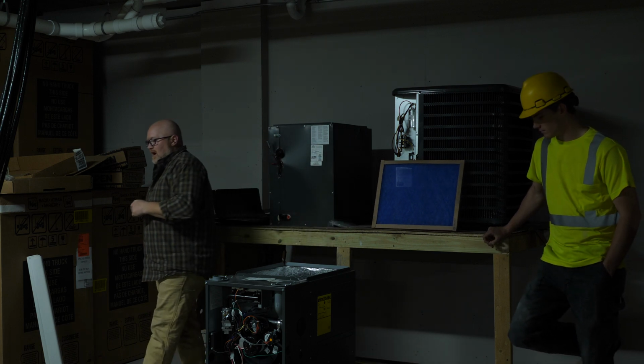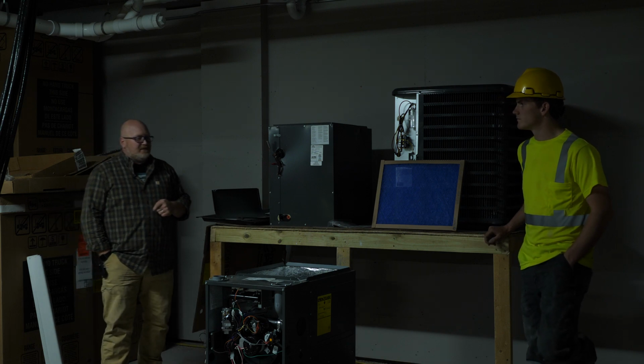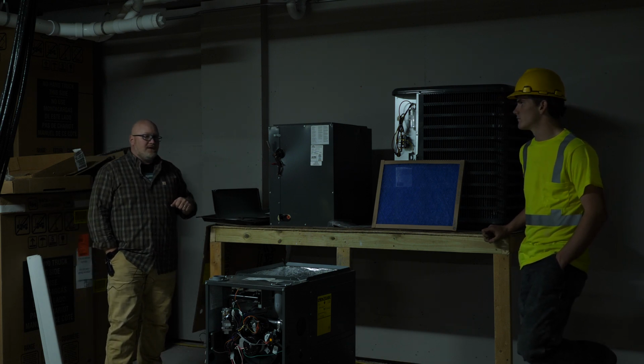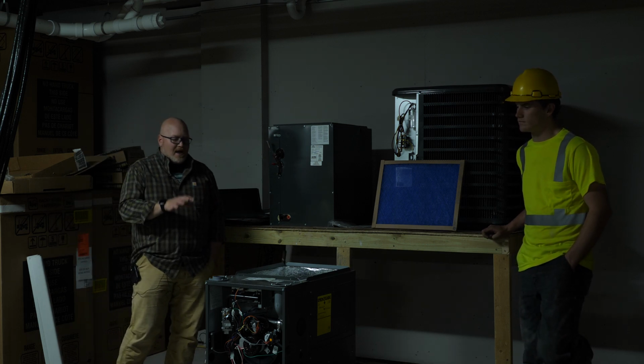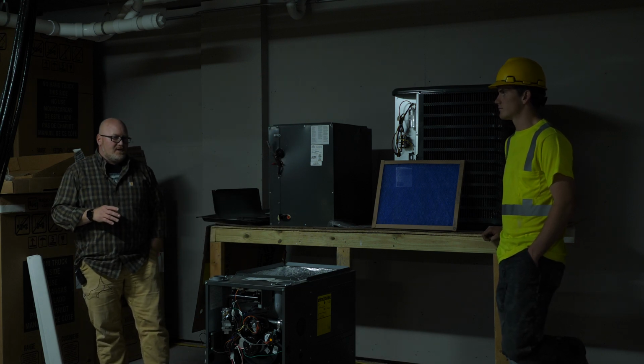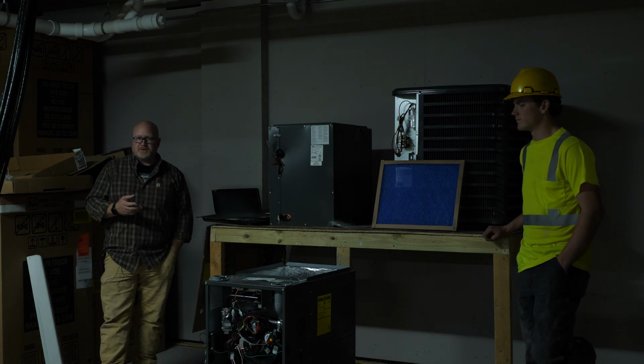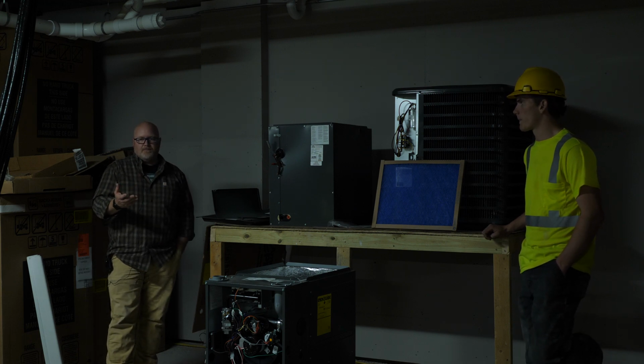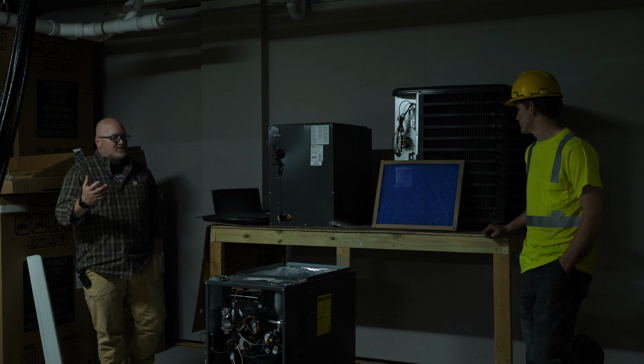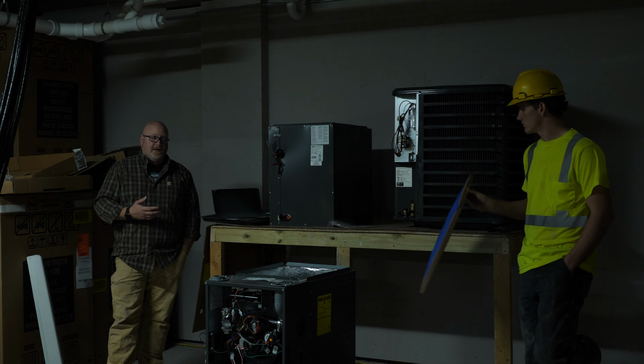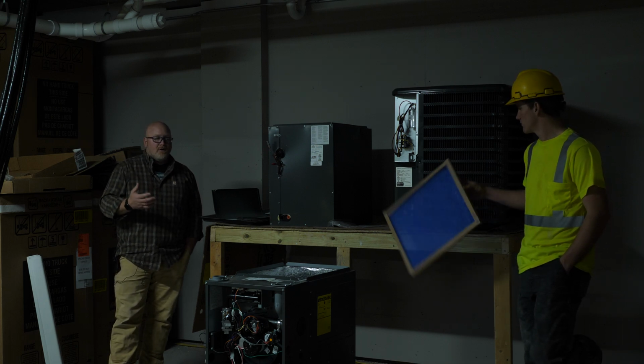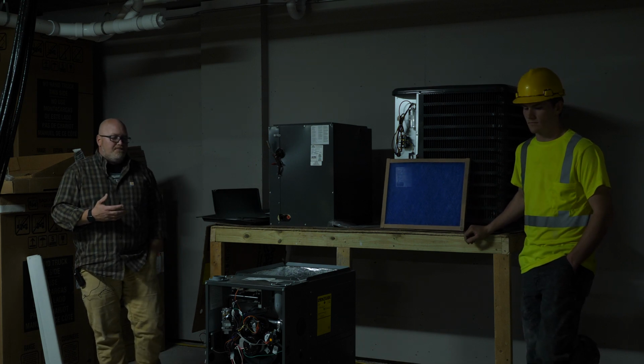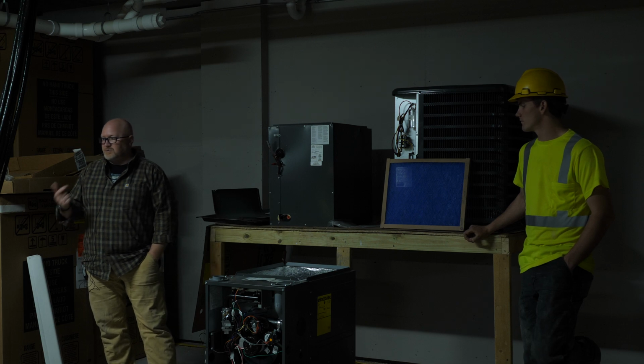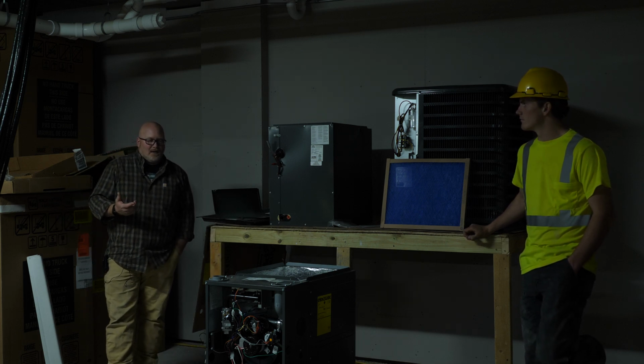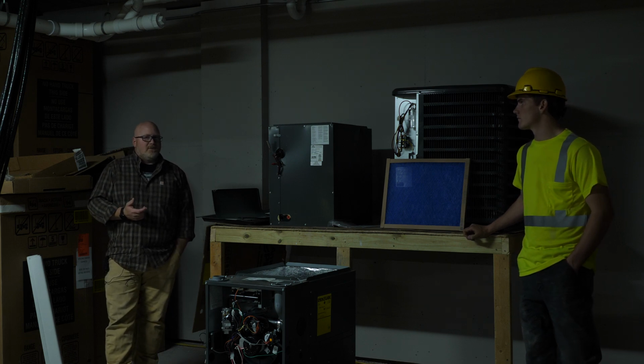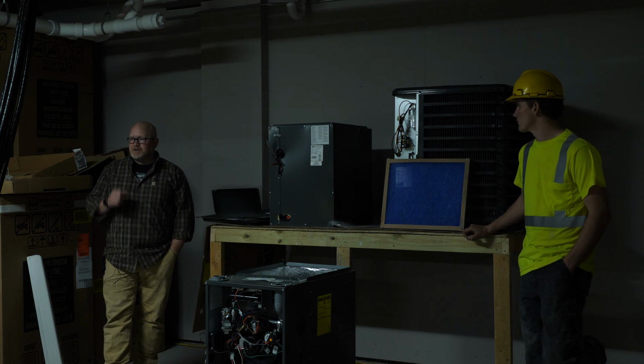I would be careful. I know some people like to go to the extreme. They like to get a MERV 14 or a MERV 20 or even a HEPA filter on their system. These systems were not designed or engineered for HEPA filters, or necessarily for super high MERV filters. MERV is another acronym used to describe the quality type of the filter. The higher the number, the more restrictive the filter is going to be. So if you're using a high MERV filter, its lifespan might be quite a bit shorter, depending on the traffic and usage of your house. Generally, I like anywhere from a MERV 8 to a MERV 11. You can find those at most of the big box stores.